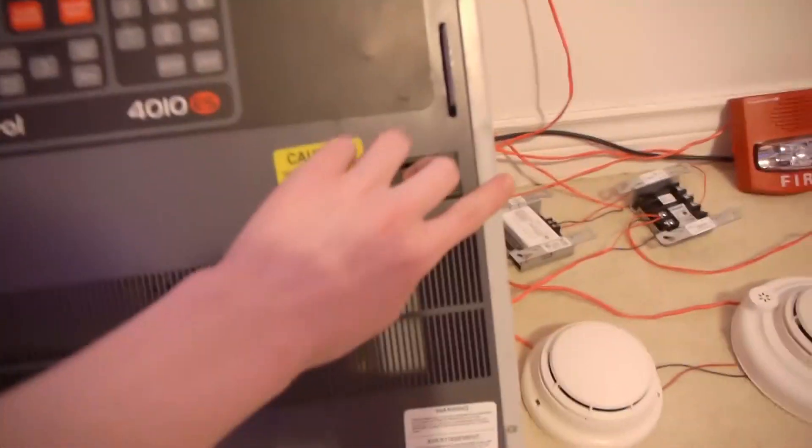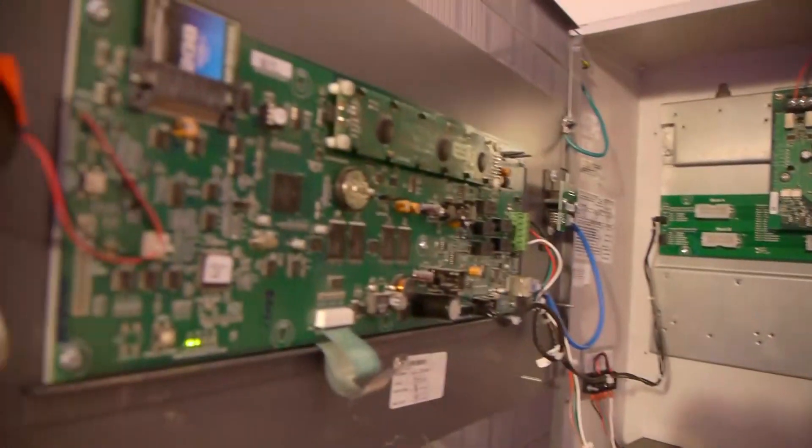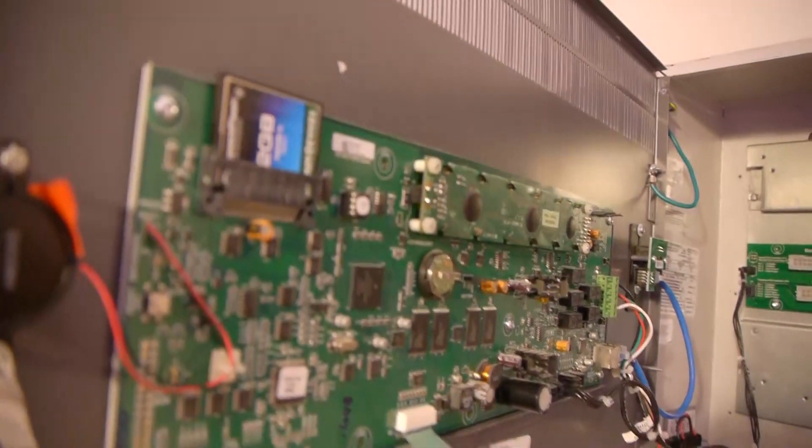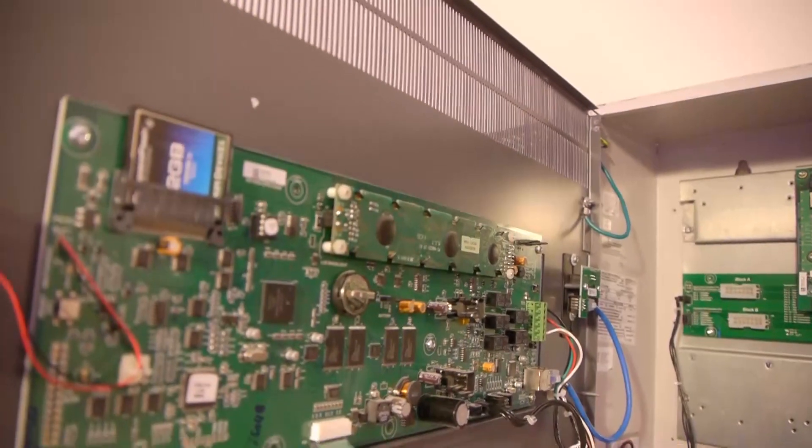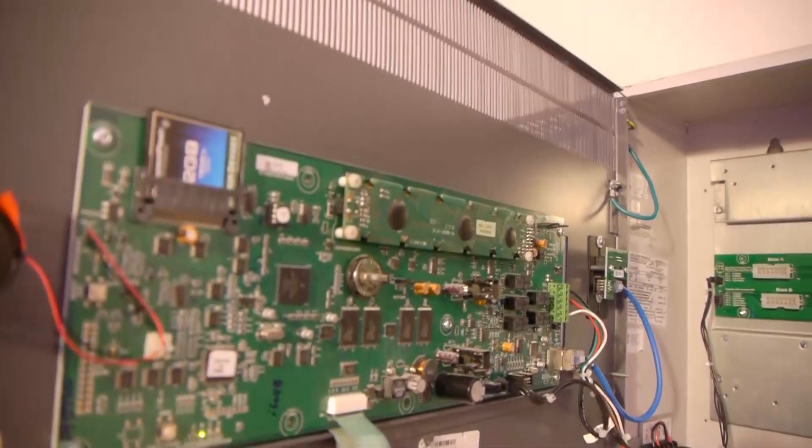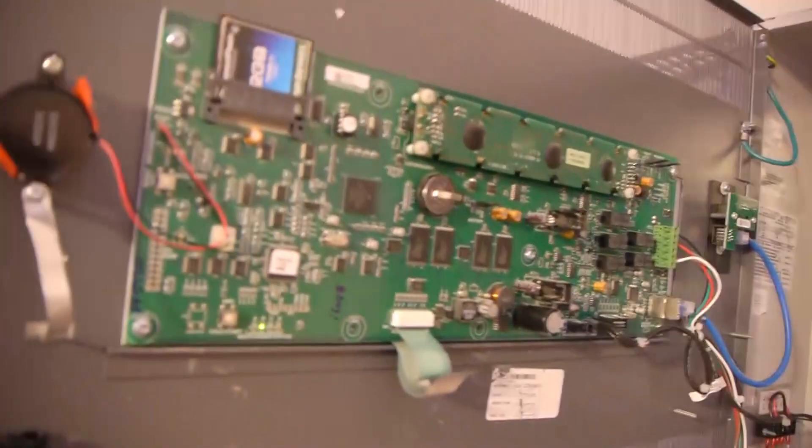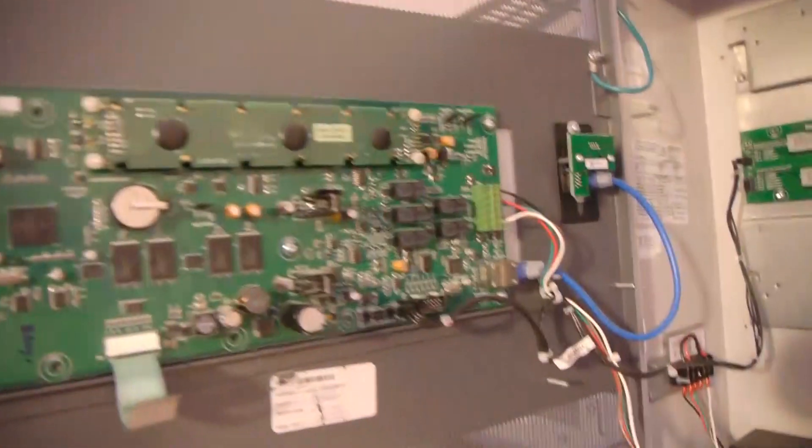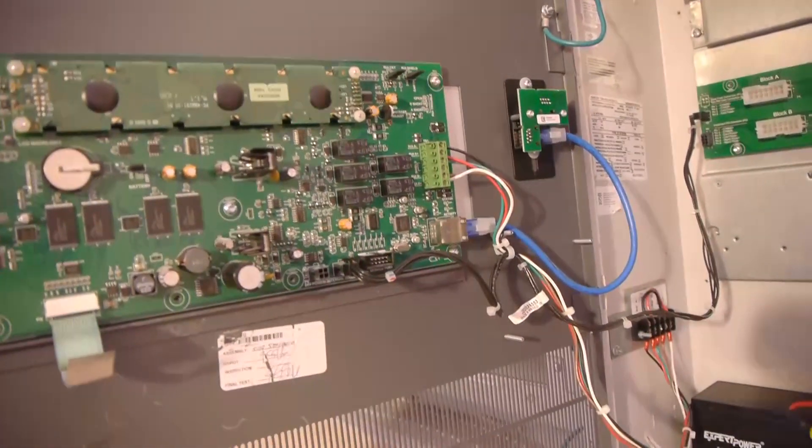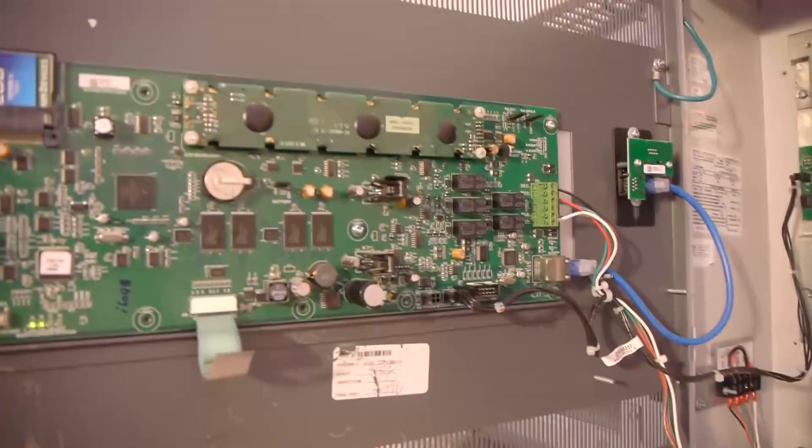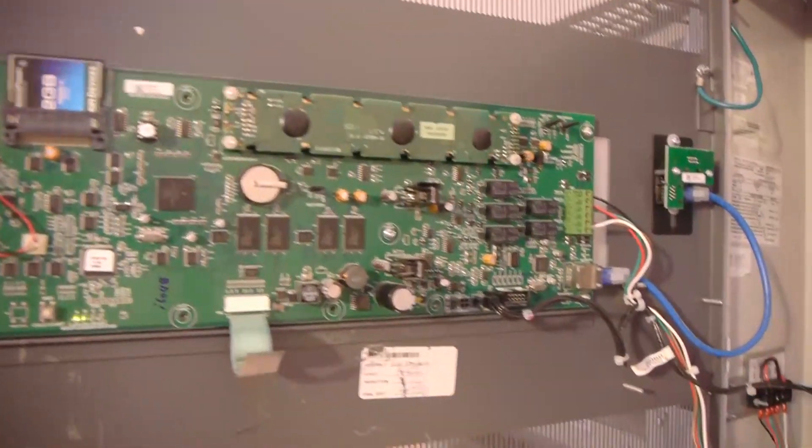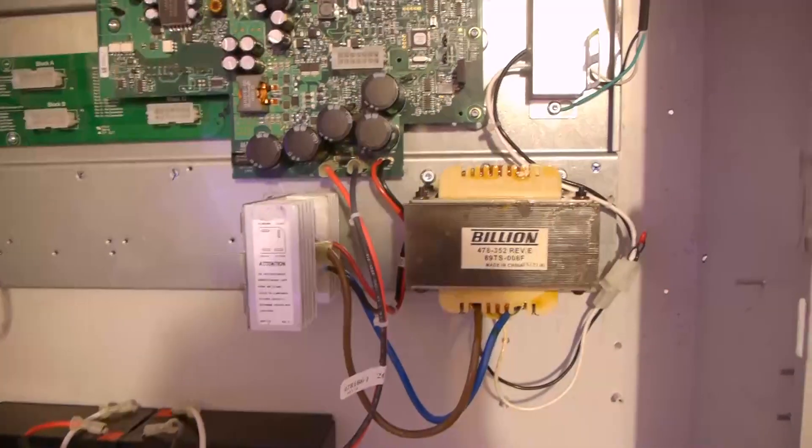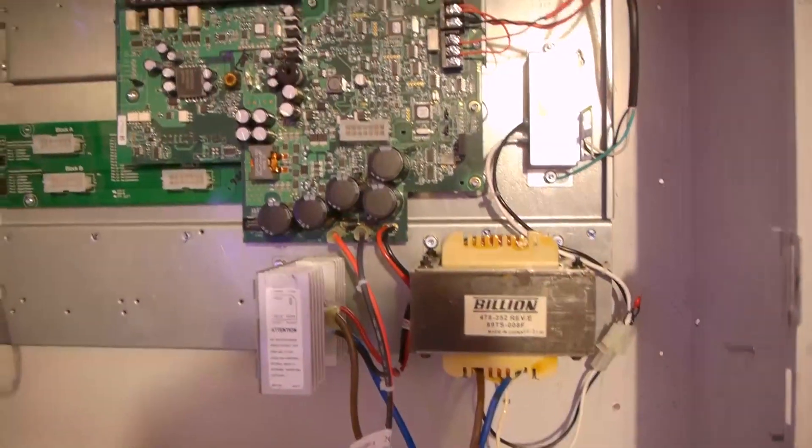So we can go ahead and open it up, you can see it has this dress panel right here with the keypad on it, and this is also where the CPU card is. You can see there's a flash card right there that stores the job, which is basically where all the configuration and programming is. You can see it's pretty simple, there's the piezo right there, ethernet port is for uploading configuration to it, there's a little coin cell battery for time and date. You can see you have batteries.